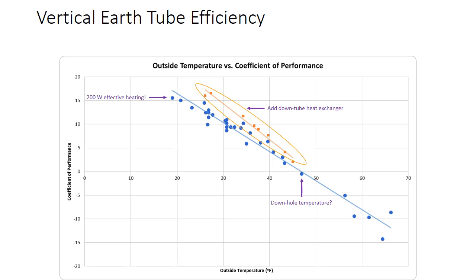Let's look at the coefficient of performance over all the measurements that we took on our earth tube over a five day period. The blue dots, first look on the left side of the plot. When the outside temperature, which is plotted on the horizontal axis, gets down below 20 degrees, that coefficient of performance is up over 15. That works out to over 200 watts of effective heating, which is pretty impressive.